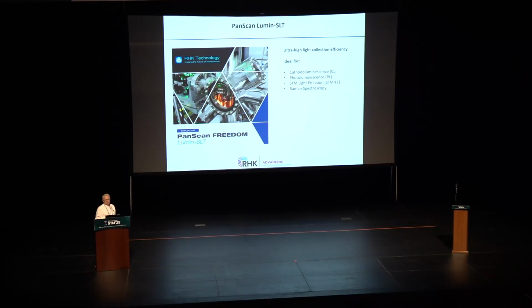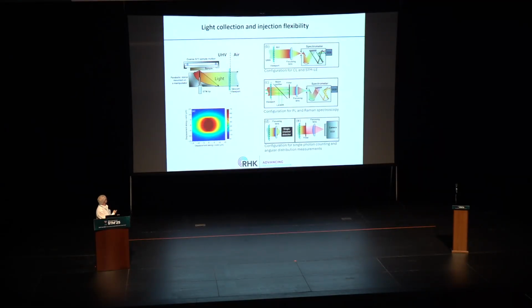The latest thing is our PanScan Lumin, which we developed in collaboration with one of our customers, with the ability to collect almost all the light coming out of the tunnel junction. The way this works is you retract the tip, and you can insert a parabolic mirror between the tip and sample, come back up inside through a hole. You can illuminate, focus the light on the tip, and you collect almost all the light coming out of the tunnel junction. The only optics in vacuum is this one parabolic mirror, and then there's an in situ XYZ positioner to align it.